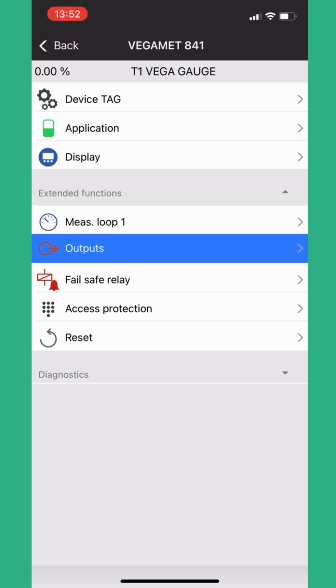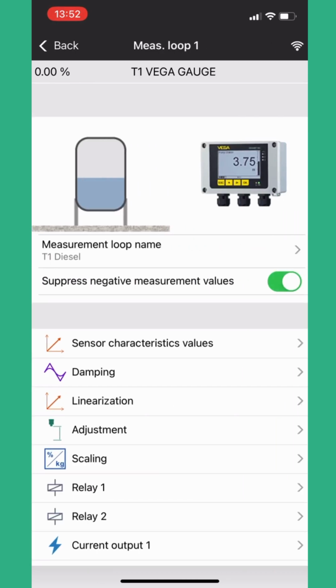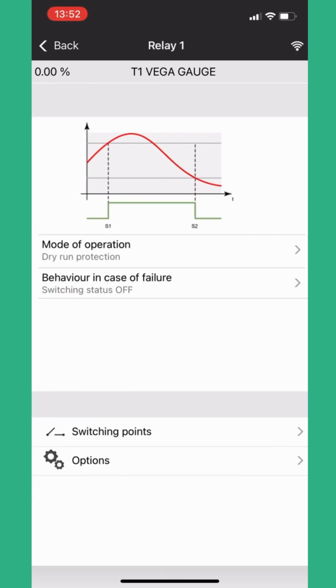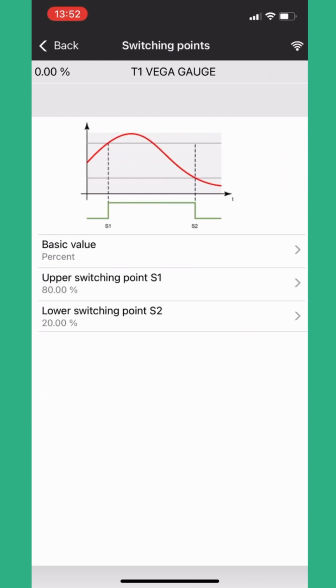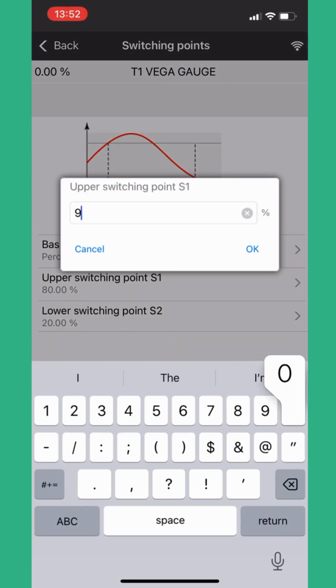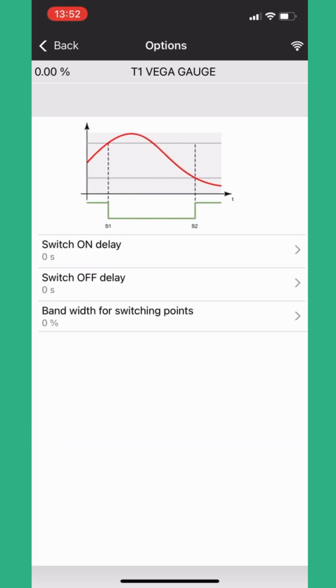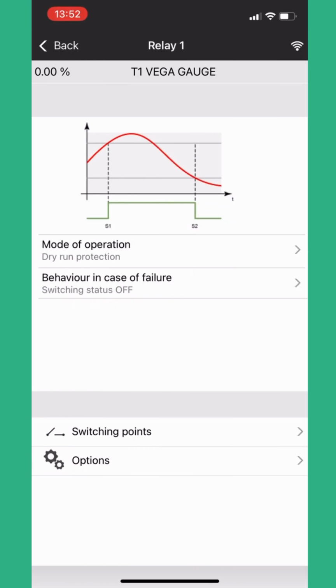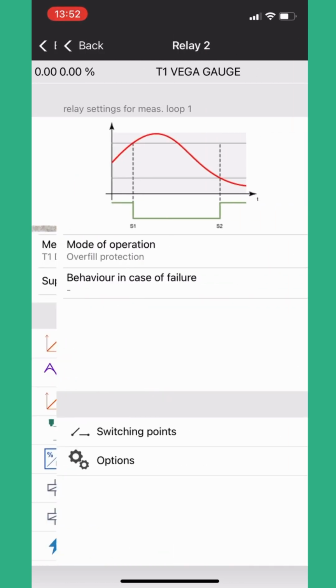Once we've done that, we go back to measuring loop 1, and we go to relay 1. For relay 1, we now have the option to change how the relay activates based on switching points. So we're going to have it switch at 90%. We can change the delay time on the relay, so we can have a few seconds delay between levels being reached and the relay activating.